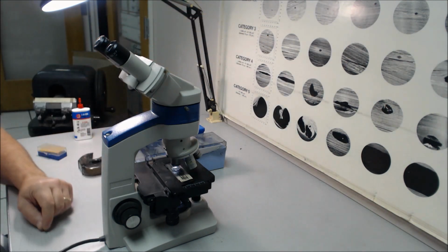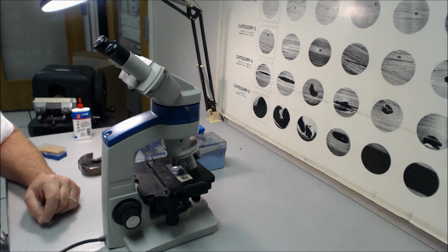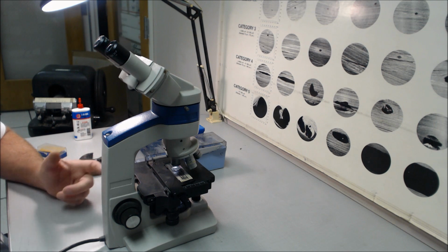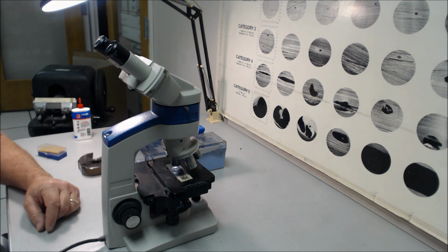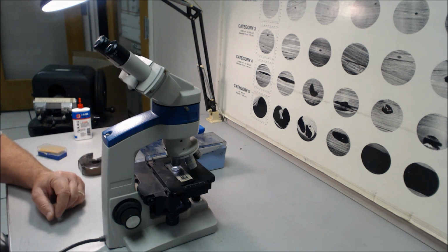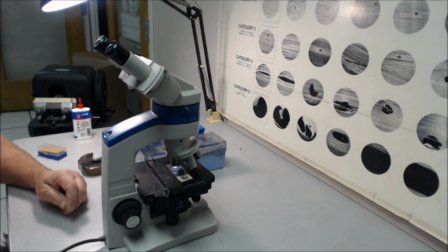You have 10 different views. You average those 10 views to the nearest 10th. And that's how the test is conducted. ASTM D5596 carbon black dispersion, and this is for GRI GM13 and 17.